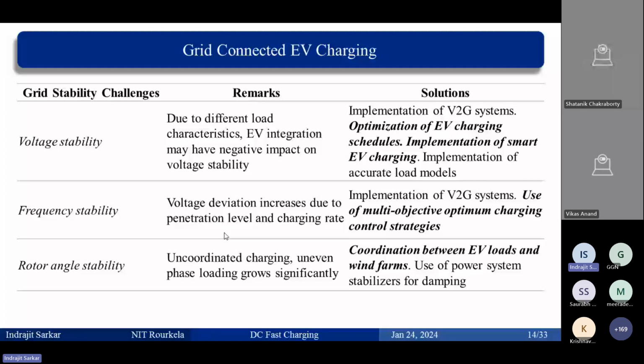Voltage failure is called voltage instability, and frequency instability is when frequency deviates. In India it's 50 hertz, so we keep it between 49.5 and 50.5. If it goes beyond that, there is instability. So how can this be mitigated?